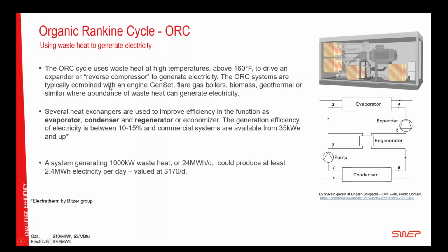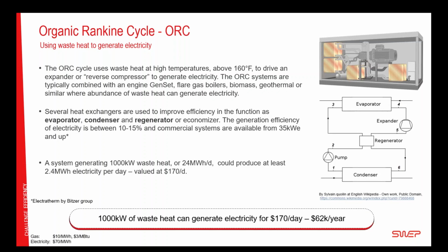So an example here, if you have 1,000 kilowatt of waste heat, which corresponds to 24 megawatt hours per day of waste heat, you will be able to produce about 2.4 megawatt hours of electricity. So a tenth in this example, valued at $170 per day. Unfortunately, I don't know the payback for this kind of system. It depends on where you can get the energy. But since the product of this waste heat is electricity and not just warm water, the economic calculus becomes stronger immediately, since we get electricity and that has a higher value. So 1 megawatt of waste heat will be able to give you $170 of electricity per day, or 62,000 per year.